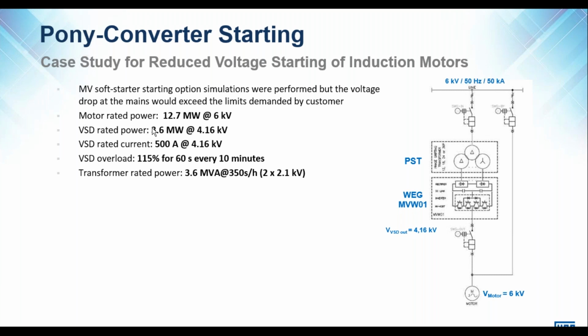And the main reason for doing this is a 6.6 kV VSD would be much more expensive. So we were able to make use of reducing the VSD's power rating, as well as dropping the voltage. Of course, we need to calculate very carefully the two in combination, because both will result in a reduction in torque during the startup of this machine. But we need to evaluate both together in order to ensure that we can get this load away.